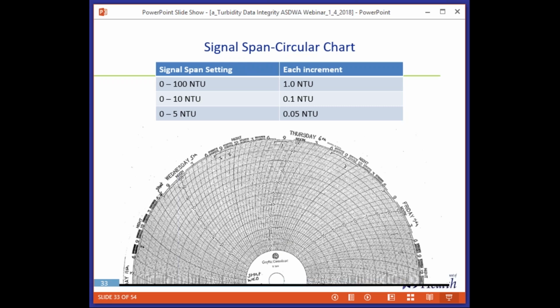So I'm going to throw in something I didn't before, which is that a lot of these instruments have 2 outputs. And so you could have 2 pens on this chart and have them set at different resolutions. So you could capture the normal operation and also if you ever had a regulatory violation.